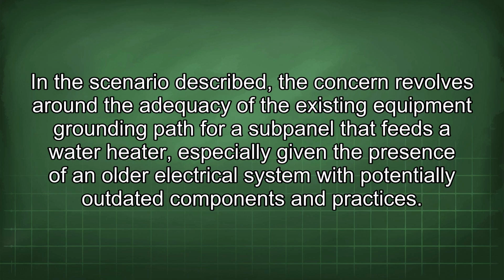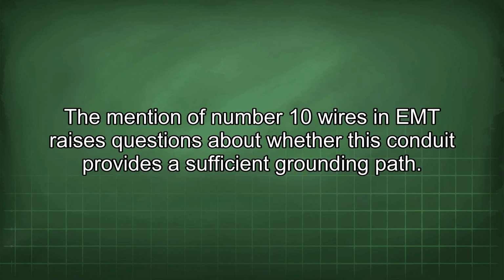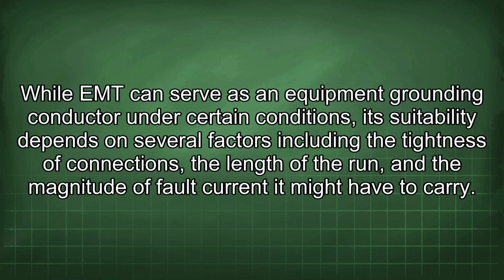In this scenario described, the concern revolves around the adequacy of the existing equipment grounding path for the subpanel that feeds a water heater, especially given the presence of an older electrical system with potentially outdated components and practices. The mention of number 10 wires in EMT raises questions about whether this conduit provides a sufficient grounding path. While EMT can serve as an equipment grounding conductor under certain conditions, its suitability depends on several factors, including the tightness of connections, the length of the run, and the magnitude of fault current it might have to carry.